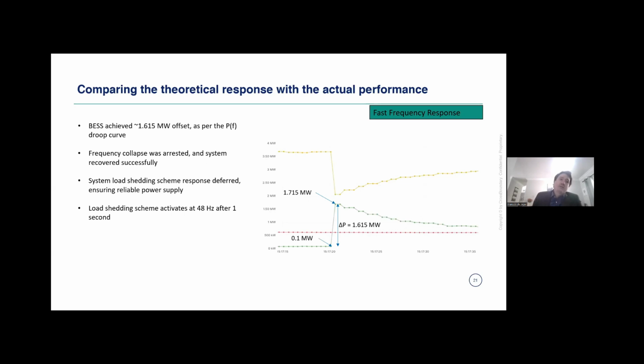If we then compare this theoretical response with the actual performance, we can see that within 500 milliseconds, which is just the measurement resolution that we're looking at here, the battery system immediately injected 1.615 megawatt, which is exactly what we expected from the system. The test was seen as successful because the frequency collapse was arrested, the system recovered successfully, all load shedding schemes were deferred, and the power supply remained online. The load shedding scheme was active after 48 hertz after 1 second, so we recovered the system well within that time.